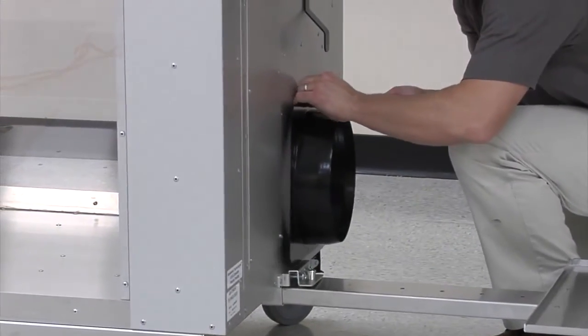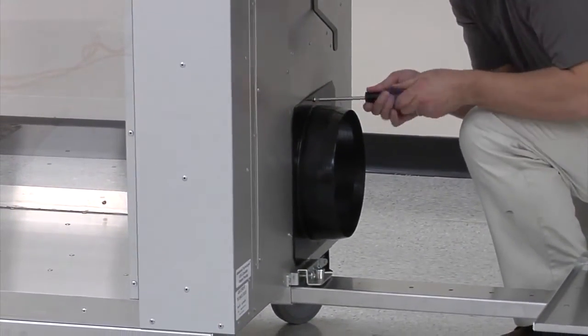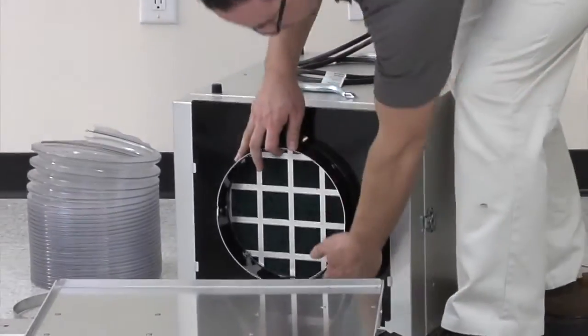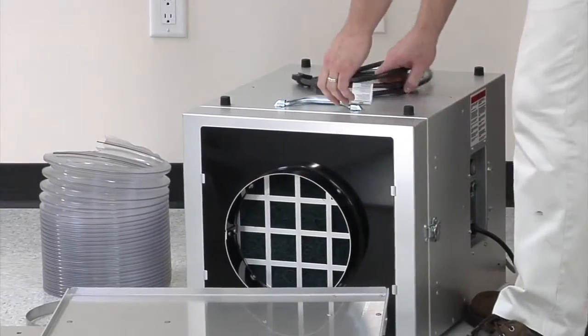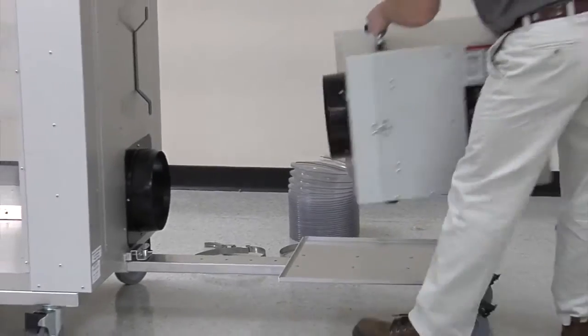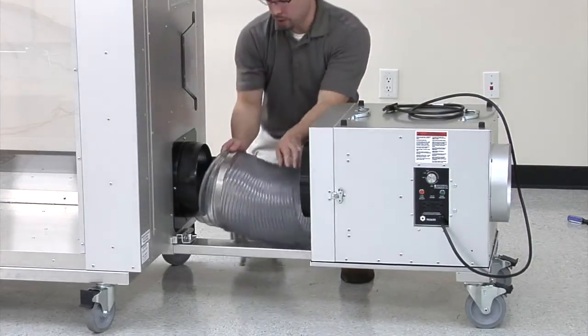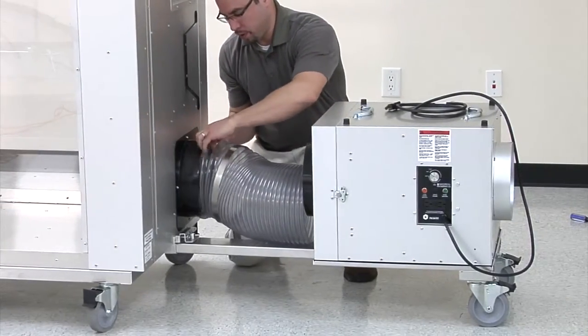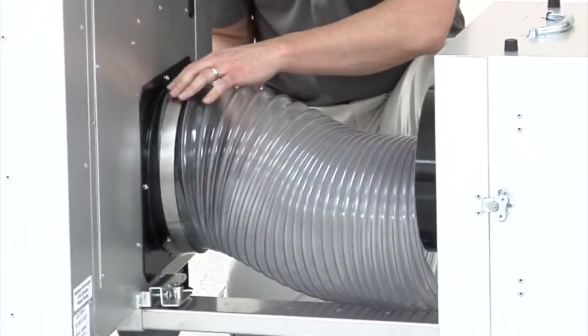Fasten the duct adapter to the AG8000. Slide the duct adapter into the tabs on the PAS600 intake door. Place the scrubber on the caddy. Attach the flex duct to the AG8000 and PAS600 and secure each with the duct clamps.